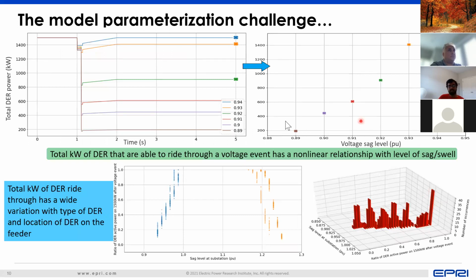So we revisit the diagram that we showed on the first slide, which showed the nonlinear tripping. Now if we translate this kind of time domain characteristic into a characteristic that still keeps the y-axis the same, the total amount of DER power, but rather than having time on the x-axis, we have these voltage thresholds. So now we are trying to characterize, for each of these voltage thresholds, how much DER is able to ride through the event and remain connected. That can translate into this kind of a characteristic.